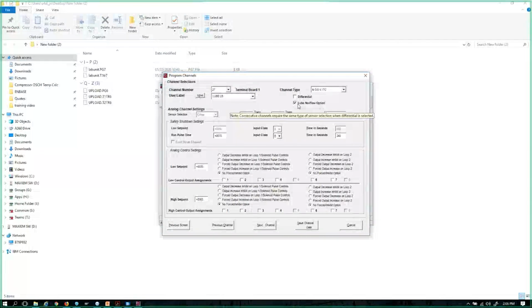The channel, like we covered last week when we covered the hardware, wires in exactly like a discrete channel, or a normally open or a normally closed channel. The dip switches are configured as normally open, normally closed. We simply wire the channel through the proximity switch. The proximity switch will open and close. And on a full cycle, the channel now will count, and the rest of the changes take place in the software. We configure the software, and this is why I call it a hybrid.